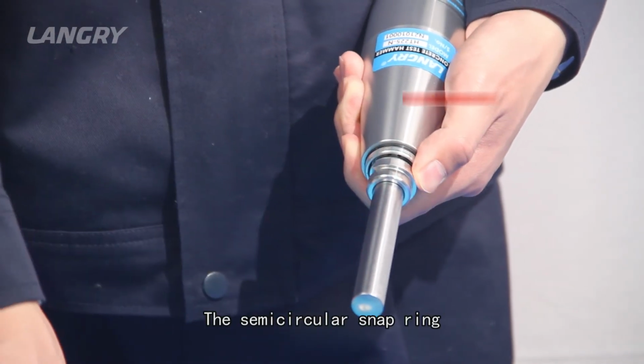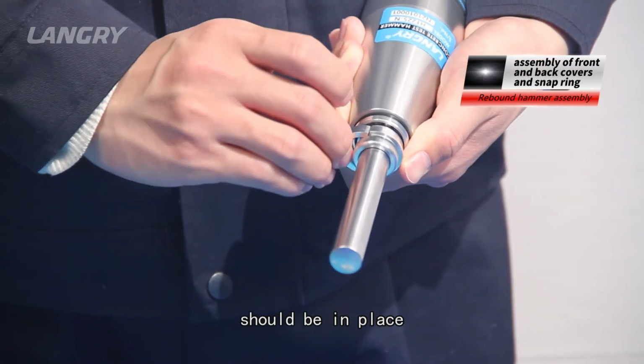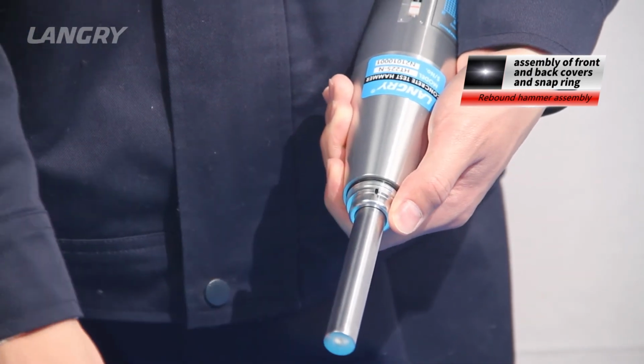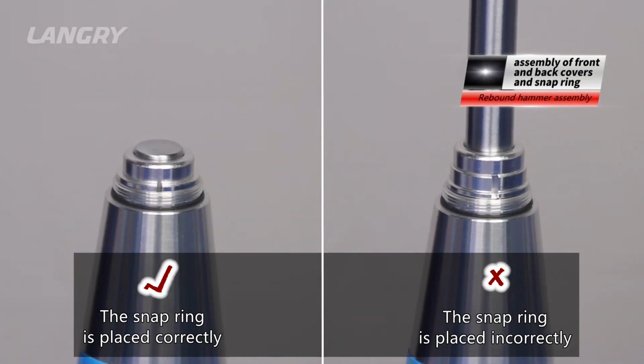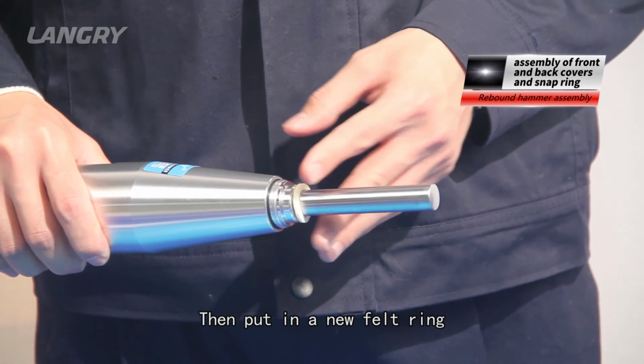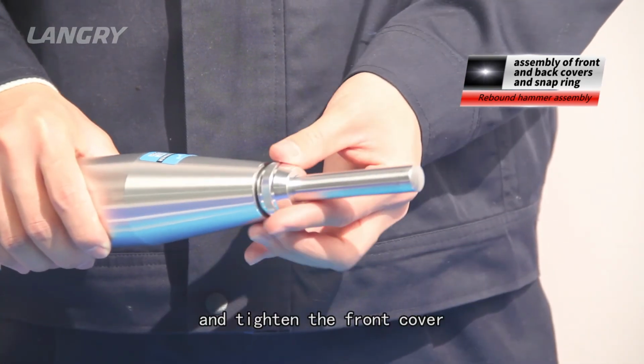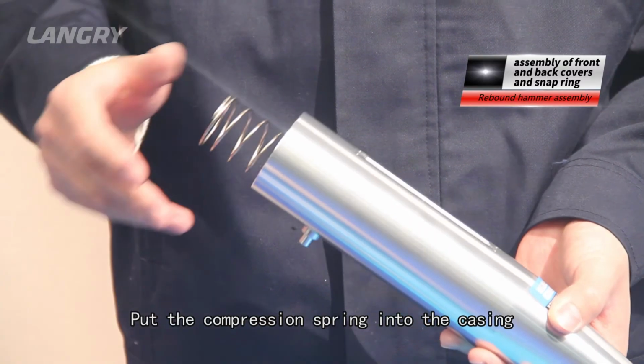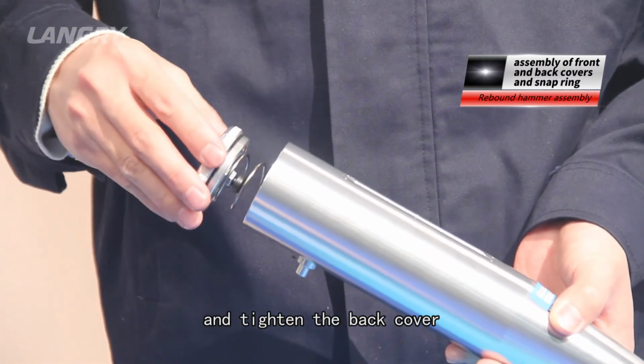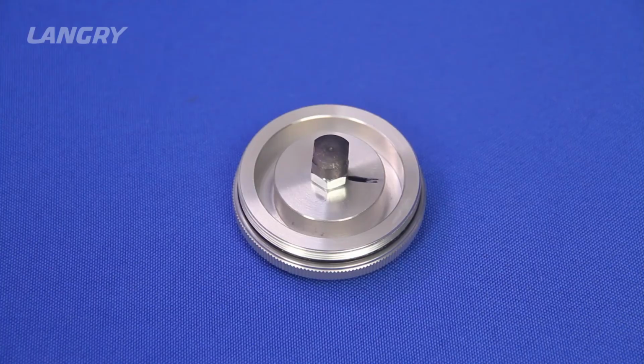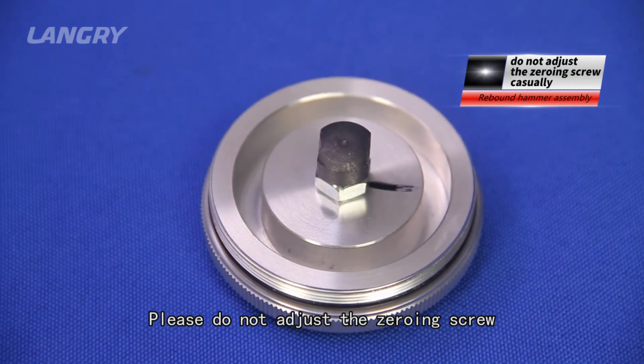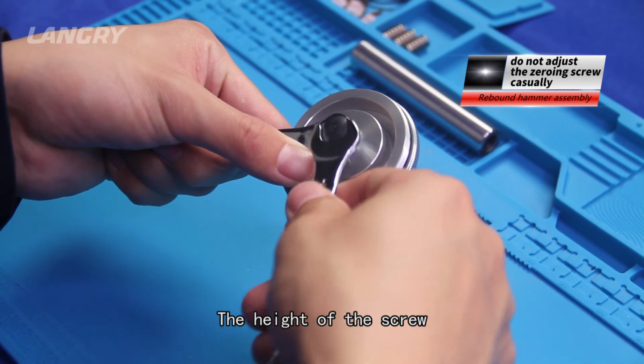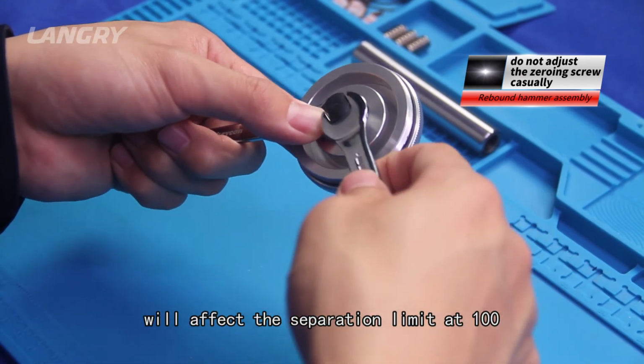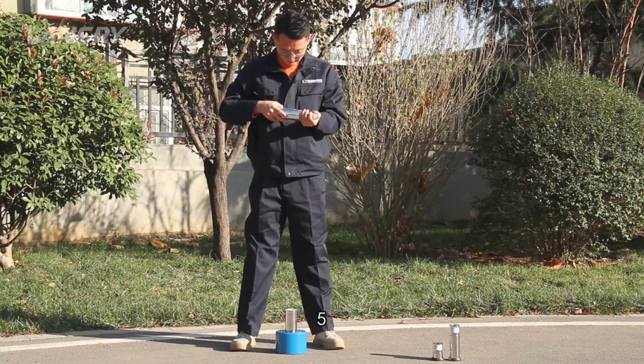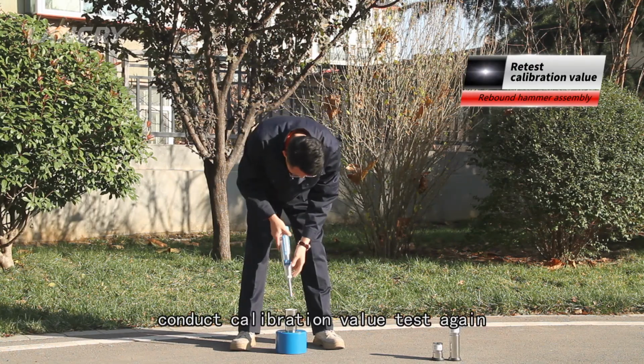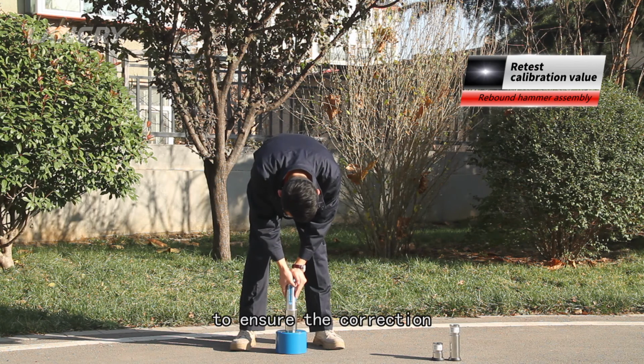3. The semicircular snap ring should be in place. Then put in a new felt ring and tighten the front cover. Put the compression spring into the casing and tighten the back cover. 4. Please do not adjust the zeroing screw at the back cover casually. The height of the screw will affect the separation limit of 100 and impact energy. 5. After assembly, conduct calibration value test again to ensure the correction.